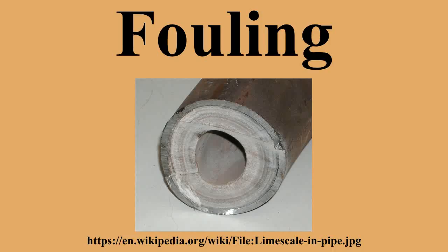Quantification of fouling. The most straightforward way to quantify fairly uniform fouling is by stating the average deposit surface loading, i.e., kilogram of deposit per square meter of surface area. The fouling rate will then be expressed in kilogram per square meter per second, and it is obtained by dividing the deposit surface loading by the effective operating time.